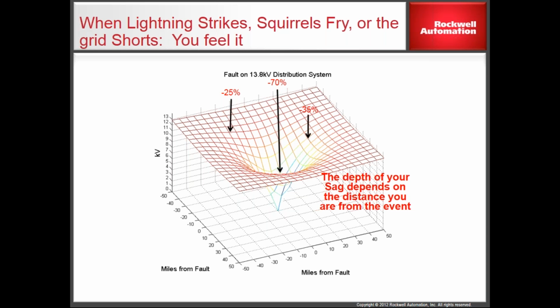The closer you are to the epicenter of the event on the wire, physically, the more it determines how deeply your voltage sags during the moment a short happens on the line. That's what makes these things so hard to troubleshoot, because every time it happens it feels different. The last time a squirrel was two miles away, the time before that a guy hit the pole twenty miles away, and tomorrow it might be next door. Every one of those events affects you differently, depending on how low that voltage goes.